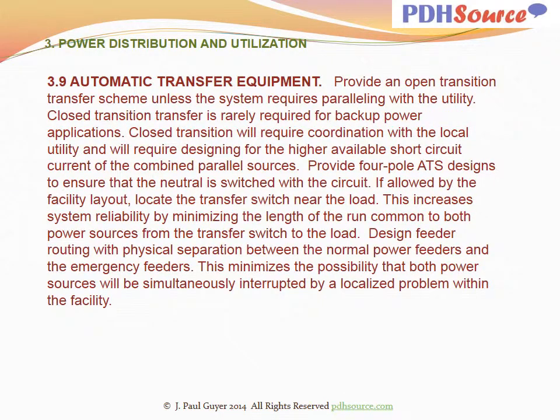With regard to automatic transfer equipment, provide an open transfer scheme unless the system requires paralleling with the utility. Closed transition transfer is rarely required for backup power applications. Closed transition will require coordination with the local utility and will require designing for the higher available short circuit current of the combined parallel sources.